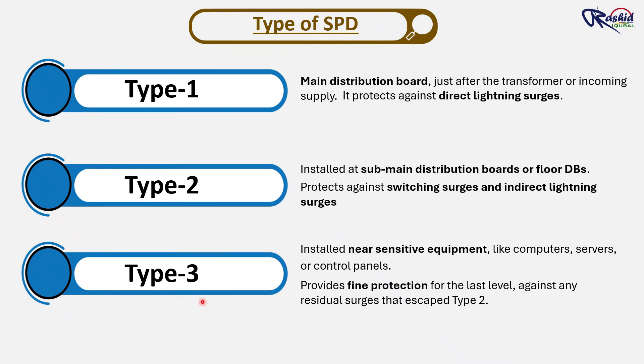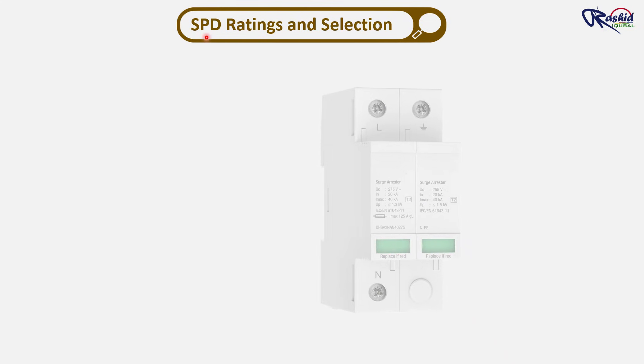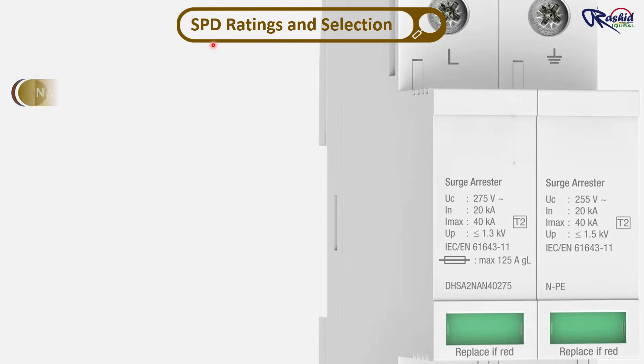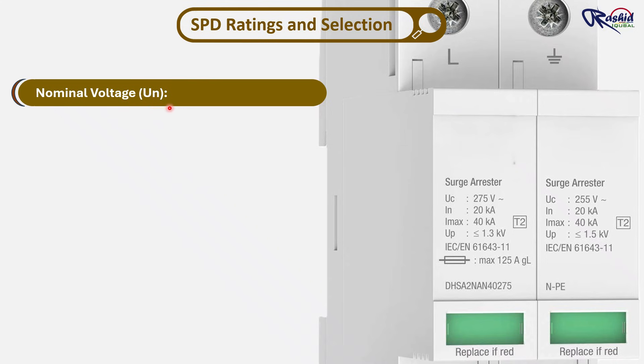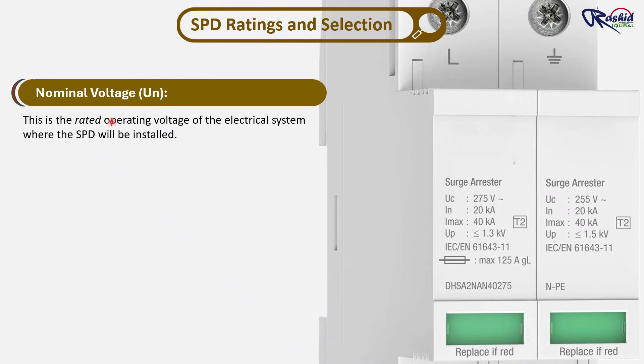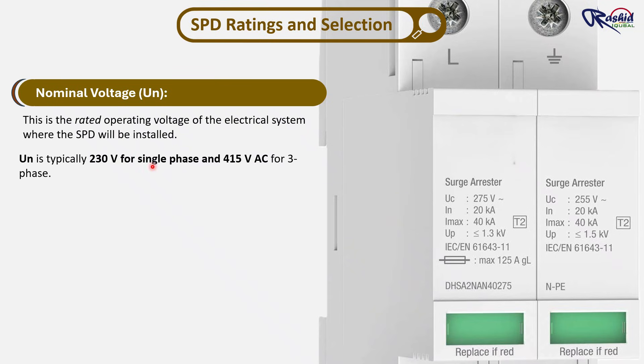Now comes the most important part: how do we select the right SPD? There are certain parameters to check. Number 1 is nominal voltage, UN. This is the rated operating voltage of the electrical system where the SPD will be installed. UN is typically 230V for single phase and 415V for three phase — the same as the system voltage.